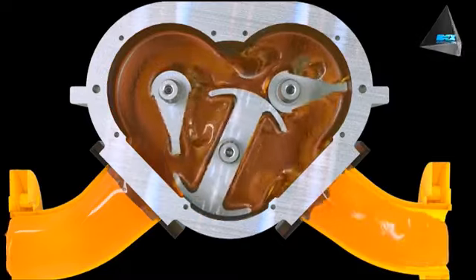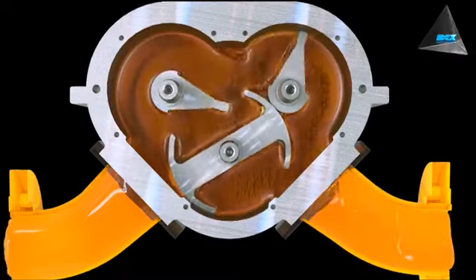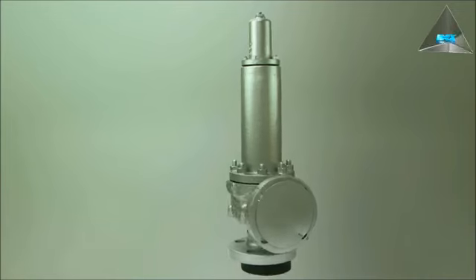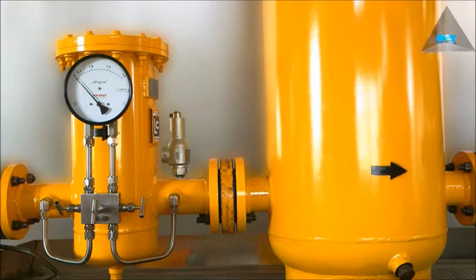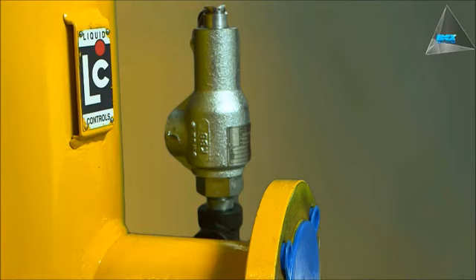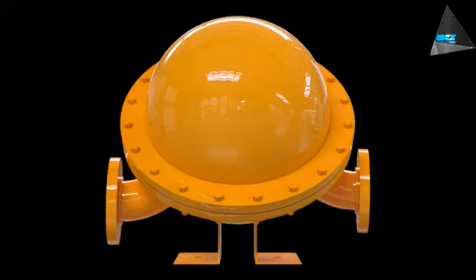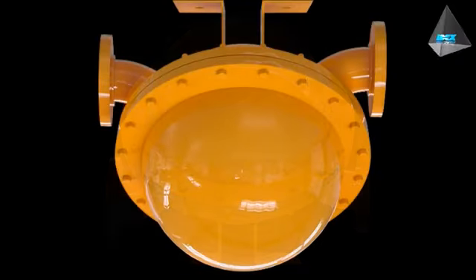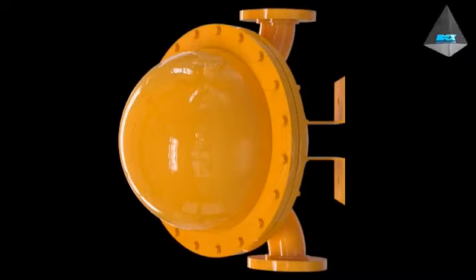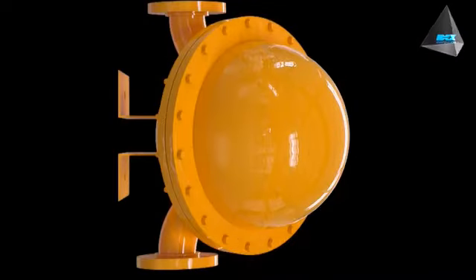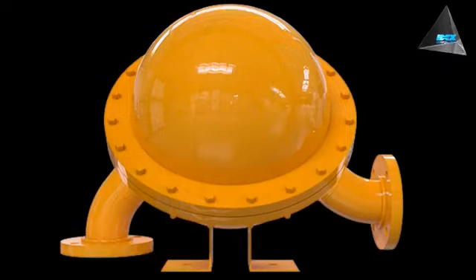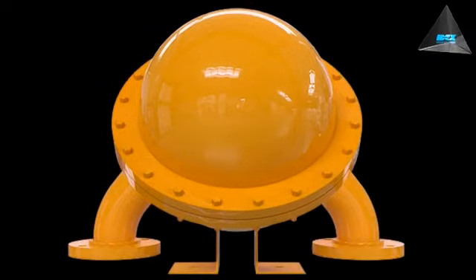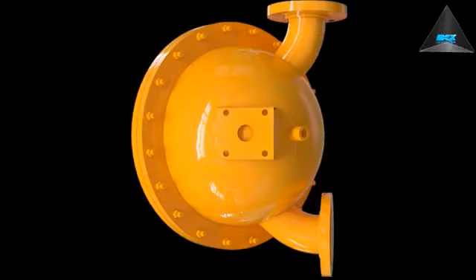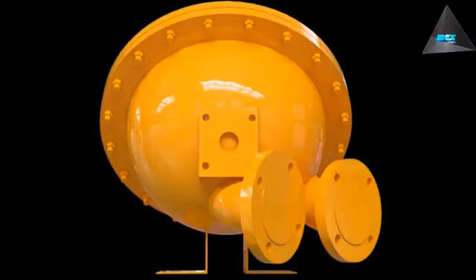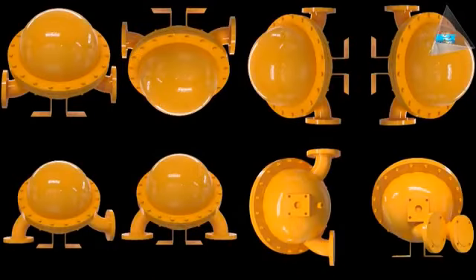The metering system should be designed to keep the meter full of liquid at all times. A thermal relief valve must be installed either on a strainer or on the air eliminator to ensure safety against thermal expansion. Variations by repositioning the flanged spool. While flanged spools are normally positioned in line for straight-through flow, many other positions are available to meet a particular installation requirement. Some of these other possible configurations are shown here. The meters operate with equal accuracy in any of the positions indicated.